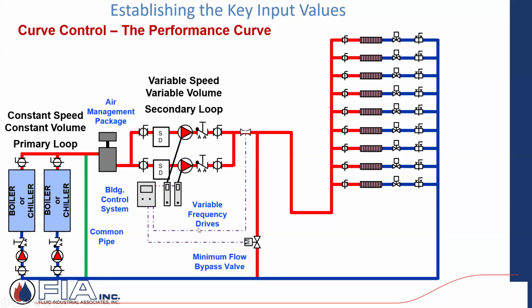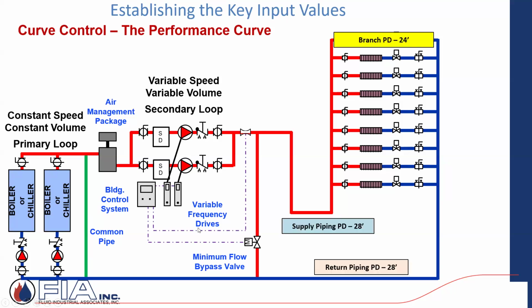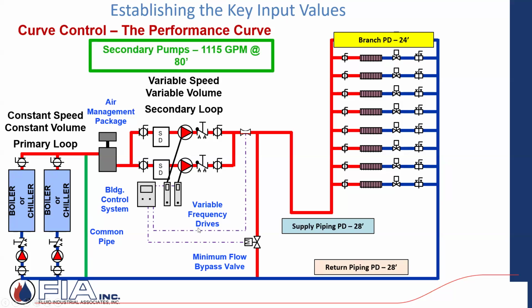The performance curve. So I have primary, secondary applications, boilers and chillers. I have my distribution, variable speed, variable volume on my secondary loop. Throwing some examples out real quick, they're saying, look, I have supply piping pressure drop and return pressure drop that equals about 56 feet of head, 28 supply, 28 return. I have a branch control head of 24 feet that I want to maintain. And so I have a secondary pump that's sized for, in this case, 1,115 gallons a minute at 80 feet of head. And of that 80 feet of head, 56 of it is variable as the flow changes, but I always want to maintain that minimum of about 24 feet of control head, control pressure drop.